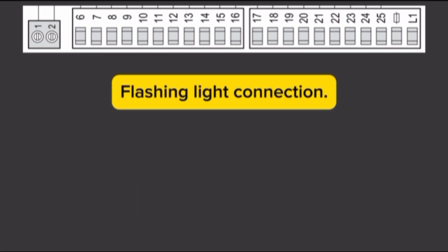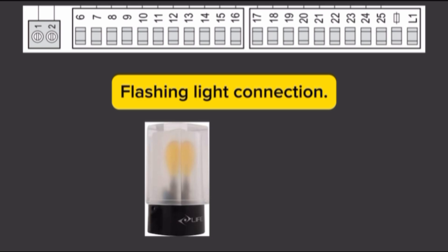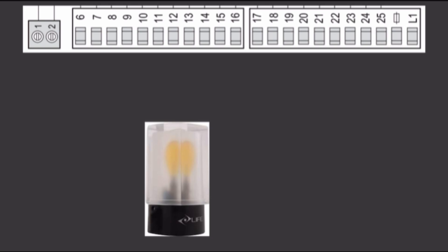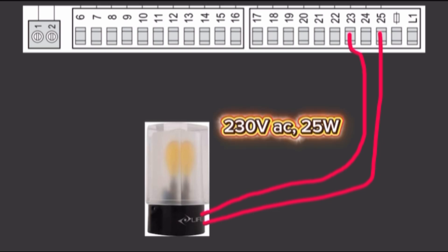Flashing light connection. Connect direct terminal 23 and terminal 25 by wire to flash pin block. Terminal 23 and terminal 25 is output 230 volt AC 25 watts max.